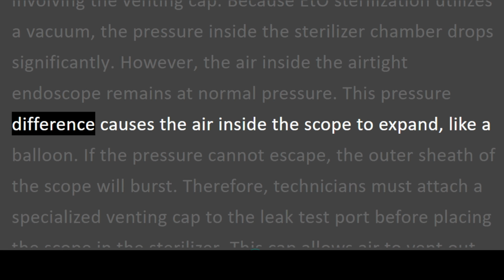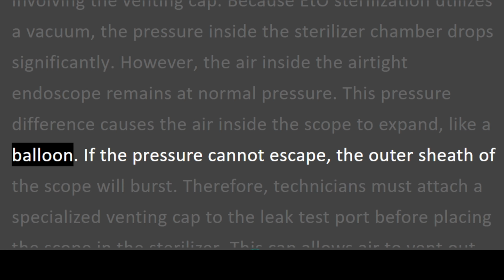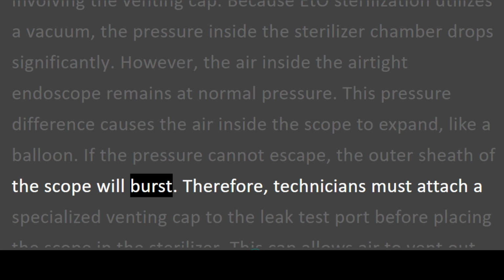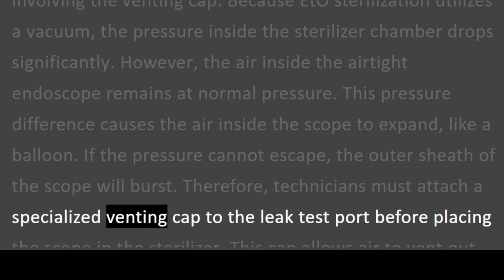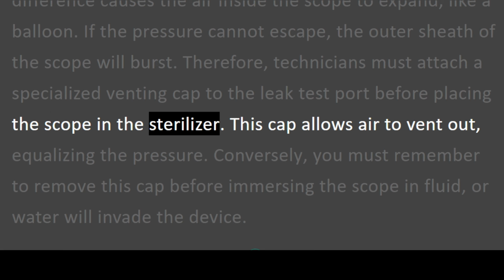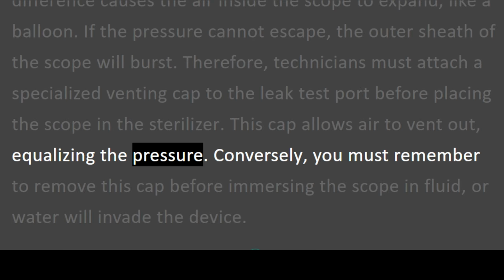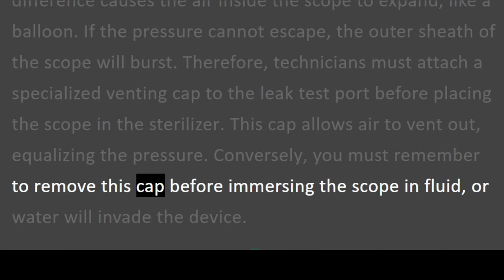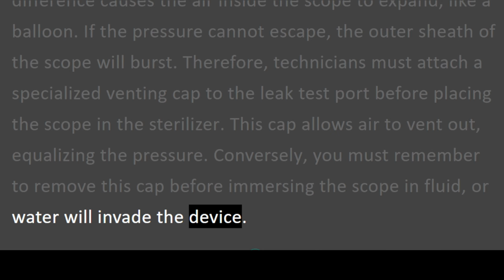This pressure difference causes the air inside the scope to expand, like a balloon. If the pressure cannot escape, the outer sheath of the scope will burst. Therefore, technicians must attach a specialized venting cap to the leak test port before placing the scope in the sterilizer. This cap allows air to vent out, equalizing the pressure. Conversely, you must remember to remove this cap before immersing the scope in fluid, or water will invade the device.